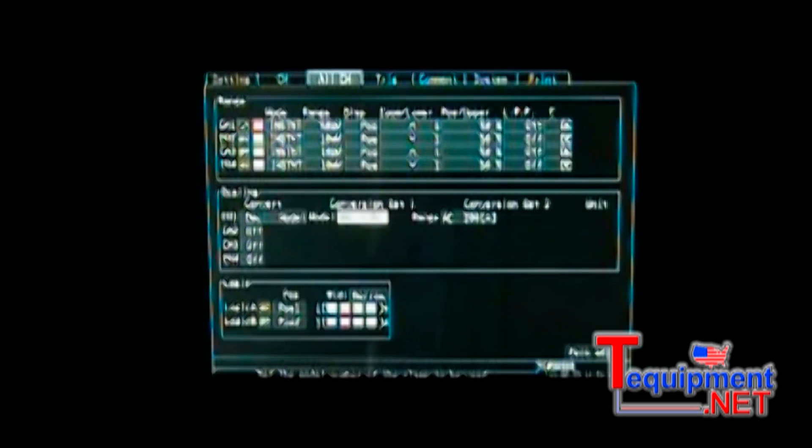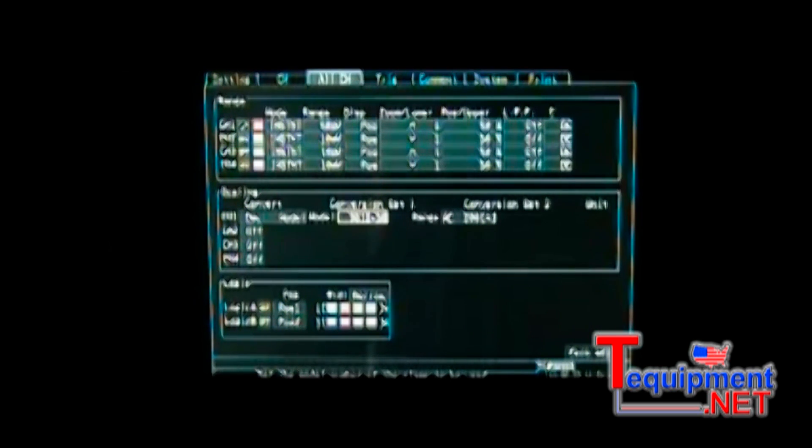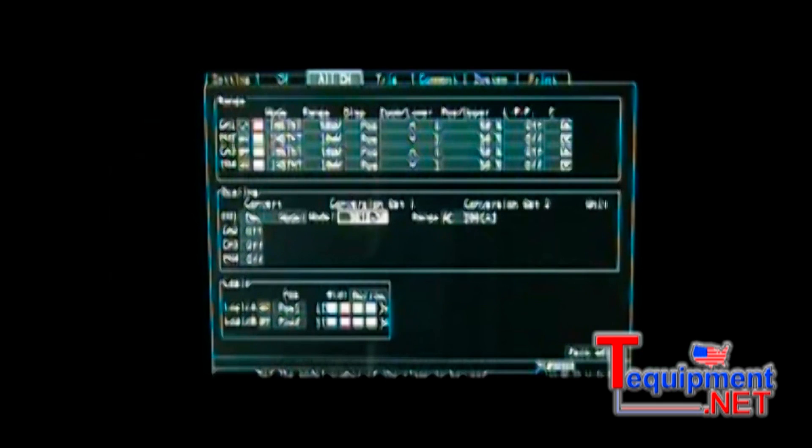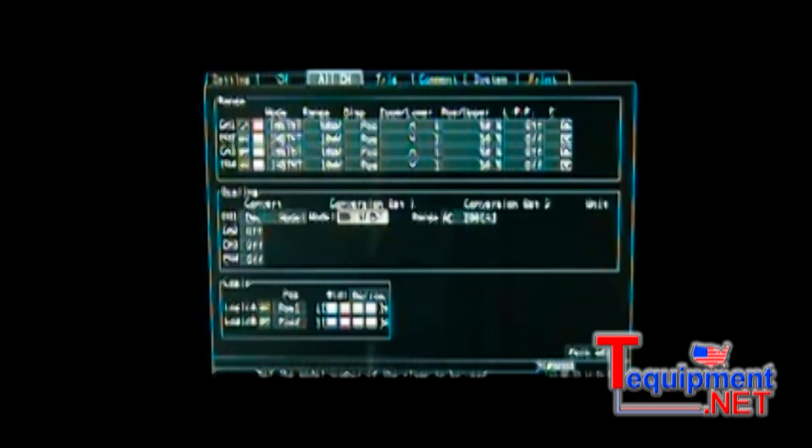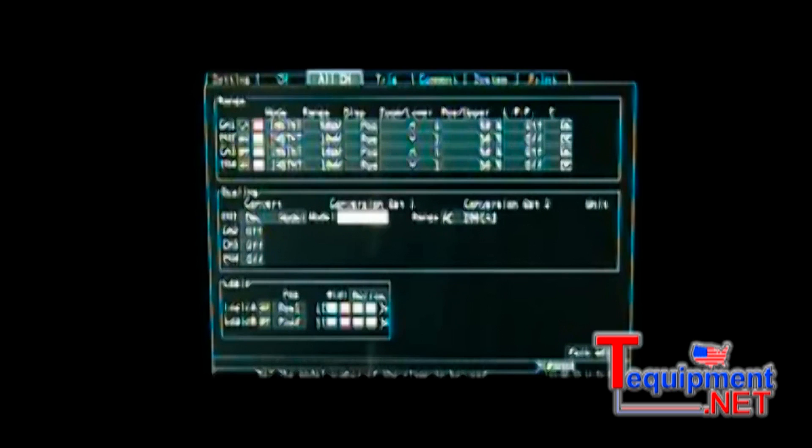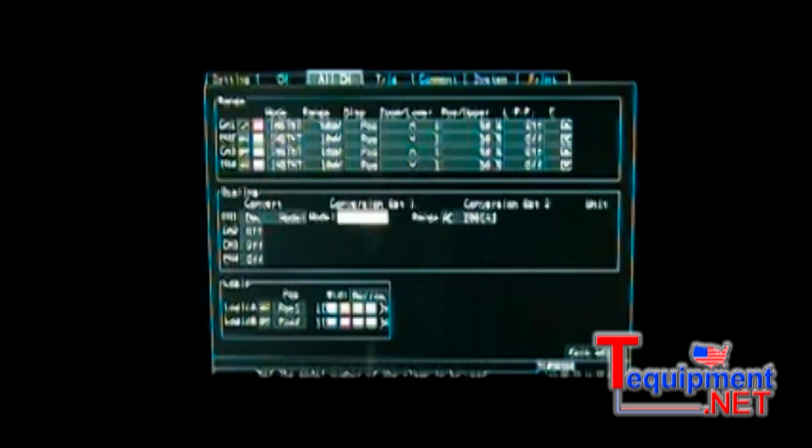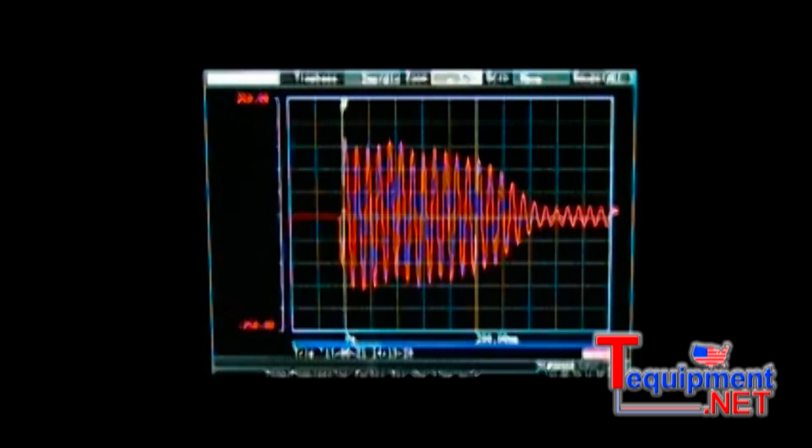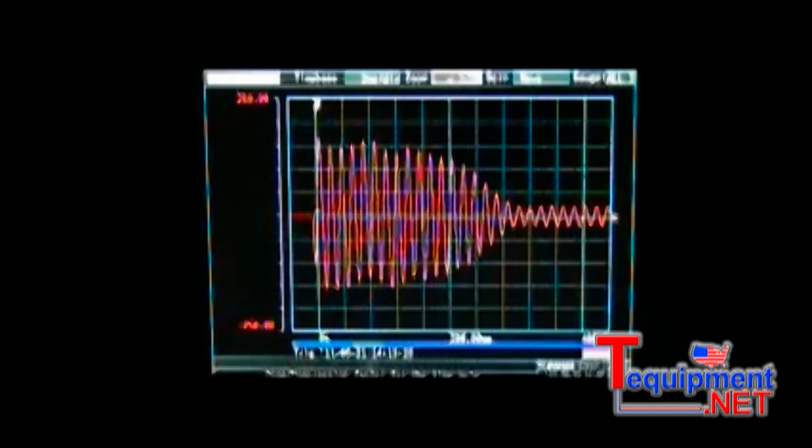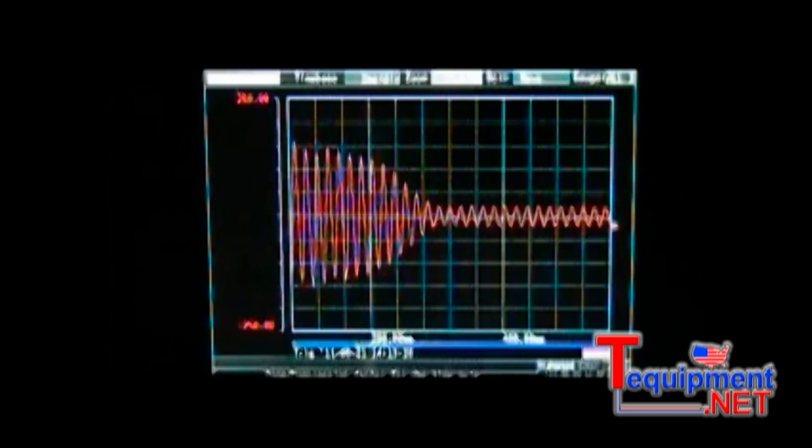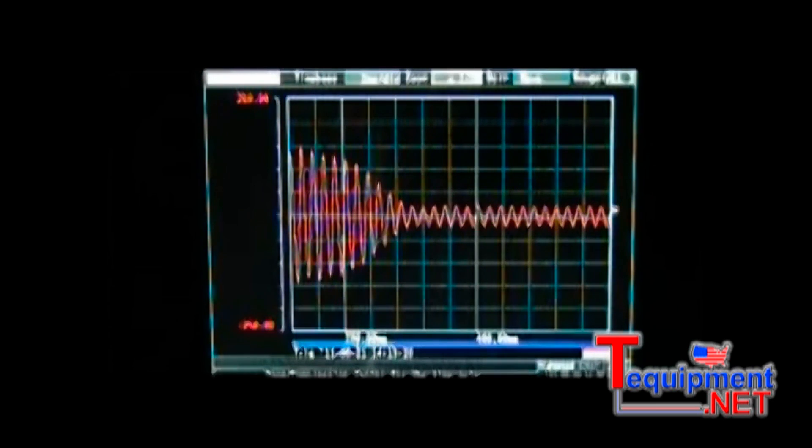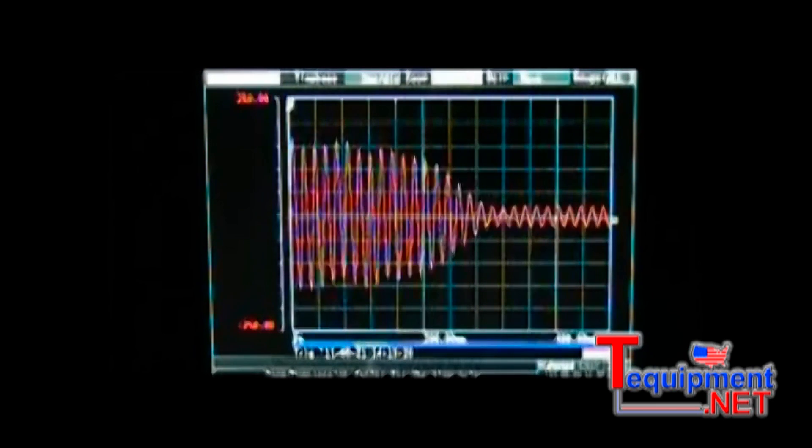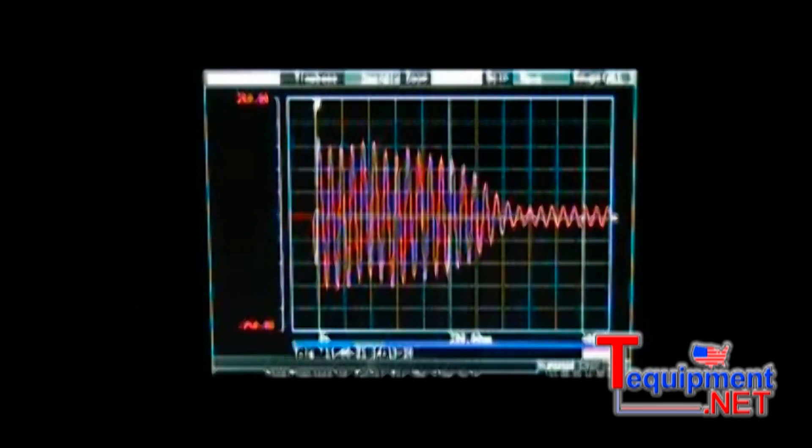Other manufacturers' clamps can also be used as long as they have a BNC connector and output a voltage representative of the current. For example, a one millivolt signal represents one amp. There are also scrolling and cursor features built into the 8880.